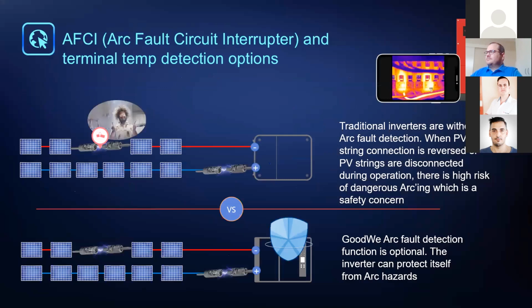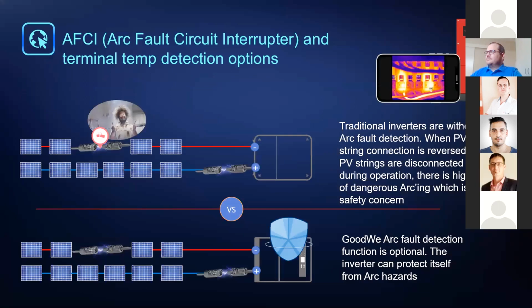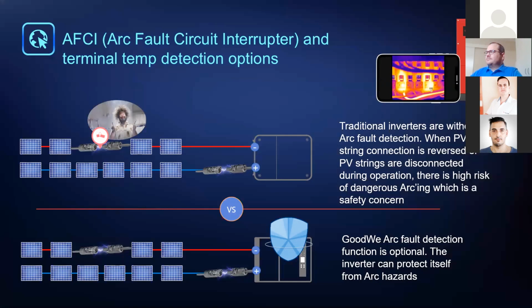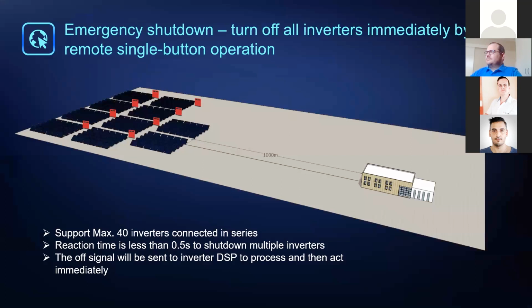Okay, your AFCI, so your arc fault circuit interrupter. Traditional inverters are generally without any arc fault detection, whereas GoodWe does have the option of arc fault detection. It's an optional extra with the inverter, but that is available. And as we know, arc faults are quite an important safety consideration, especially with the DC associated with PV systems. And then also, as I've mentioned, an emergency shutdown or a remote shutdown of the inverter is also an option.